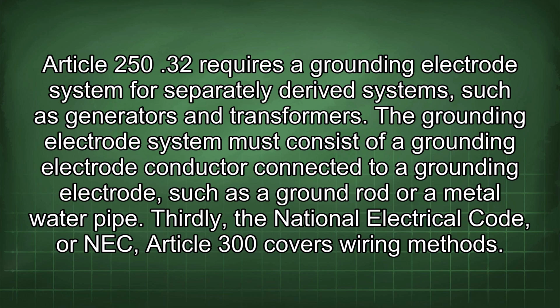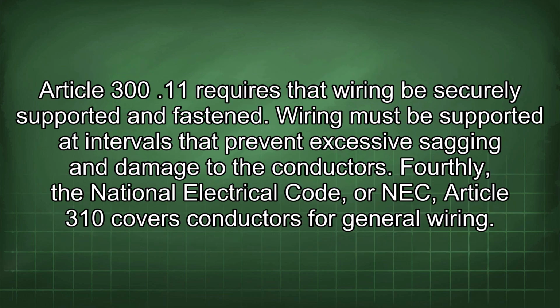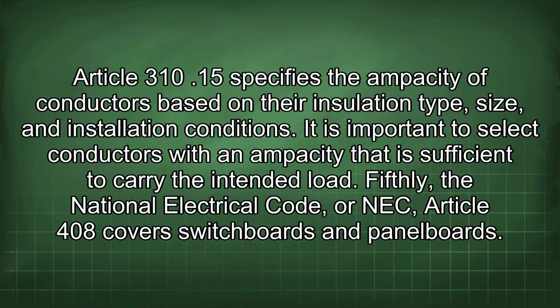Thirdly, the National Electrical Code, or NEC, Article 300 covers wiring methods. Article 300.11 requires that wiring be securely supported and fastened. Wiring must be supported at intervals that prevent excessive sagging and damage to the conductors. Fourthly, the National Electrical Code, or NEC, Article 310 covers conductors for general wiring. Article 310(15) specifies the ampacity of conductors based on their insulation type, size, and installation conditions. It is important to select conductors with an ampacity that is sufficient to carry the intended load.